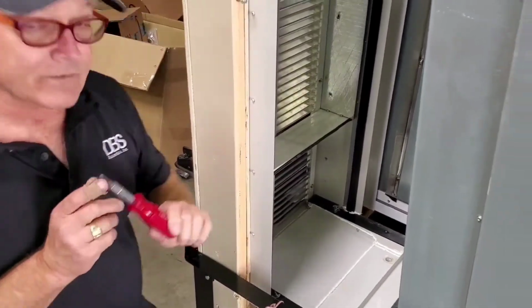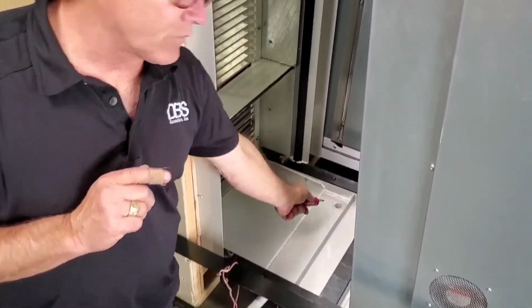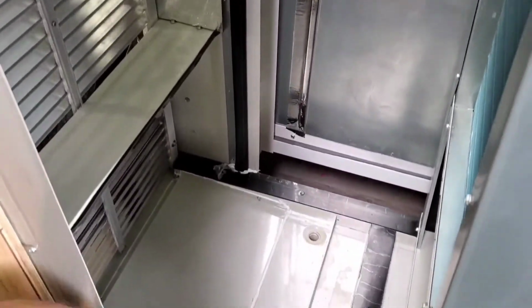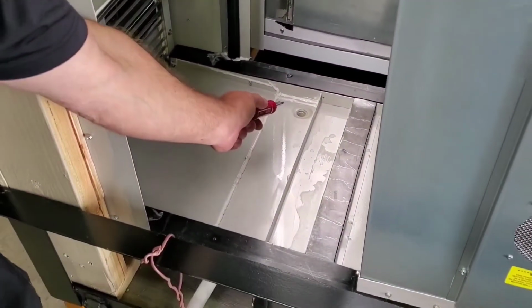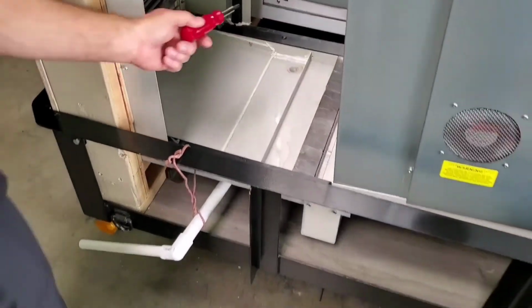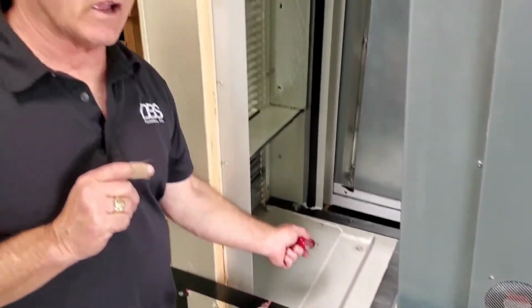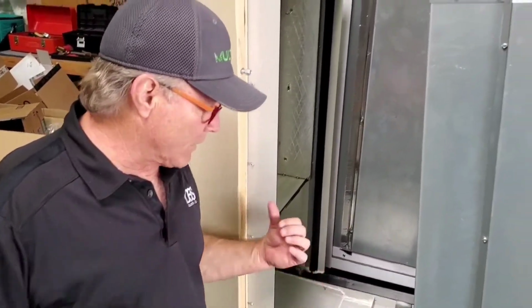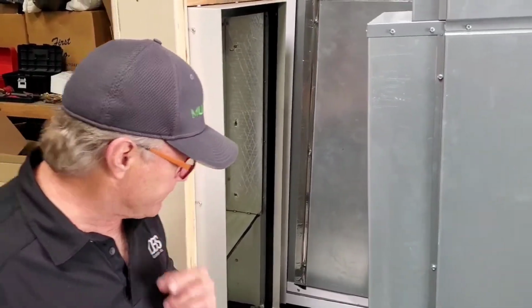One of the most important things down here is the condensate drain. That's over here. Below that, there's about a 6 to 12 inch area above the floor. There's going to be a P-trap right there. Now's the time to take your nitrogen or your CO2 and blow out that drain so it's clear and won't be leaking on the outside of the building as the overflow should do.